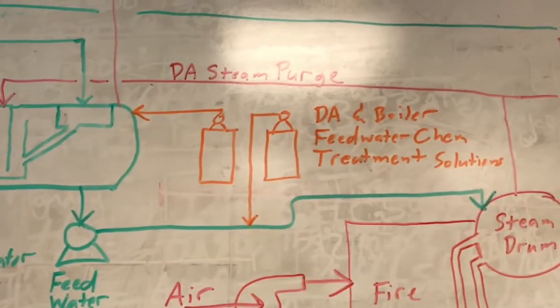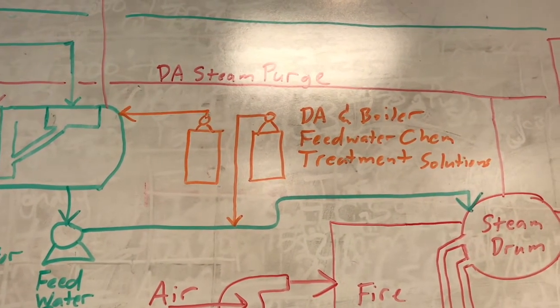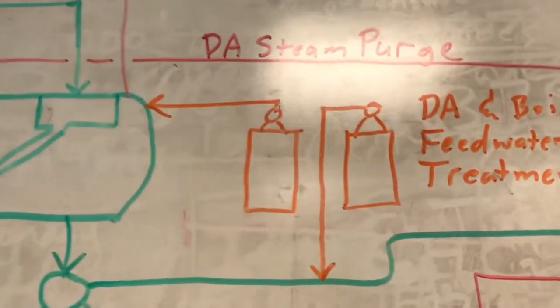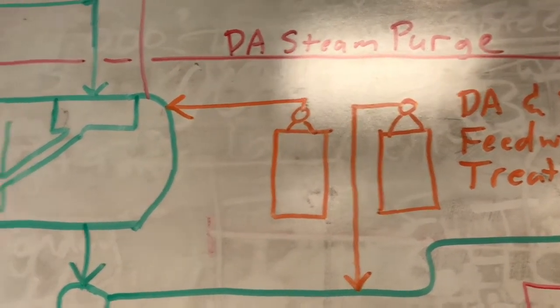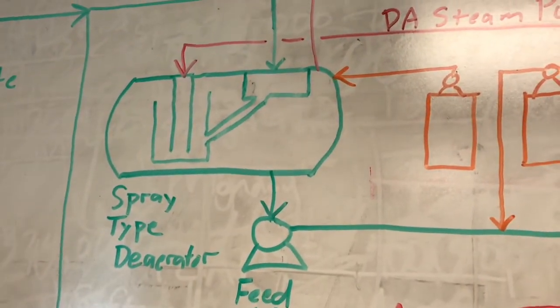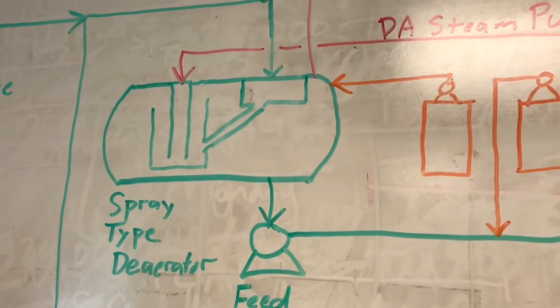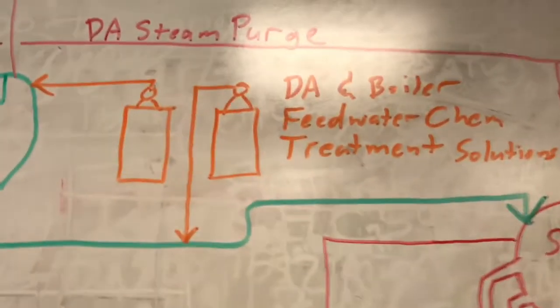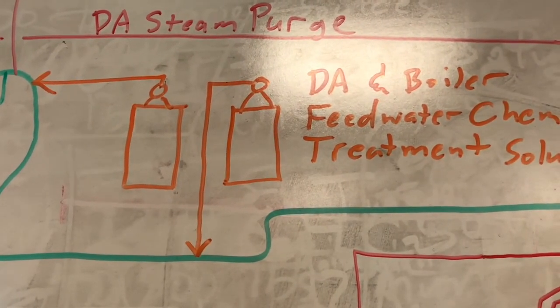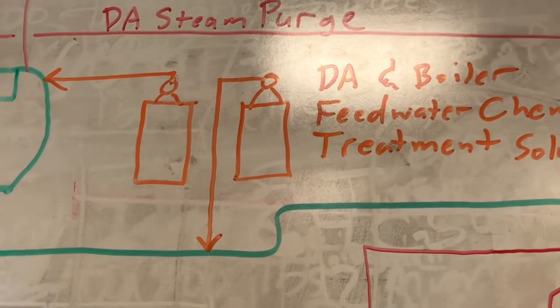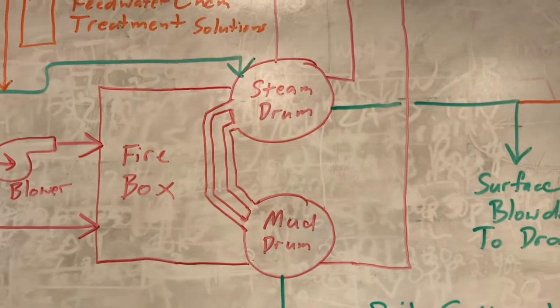In addition to that, we have two smaller liquid input streams. Boilers require chemical treatment to prevent corrosion, scaling, and other problems. We have a small sulfite solution drum with a metering pump — that sulfite solution gets injected into the deaerator to scavenge any remaining oxygen the deaeration process doesn't eliminate. We also have another drum with a cocktail of various ingredients that prevent corrosion, scaling, and other boiler issues, including pH adjustment via a small amount of caustic. These get fed into the feed water going into the boiler to keep the boiler healthy.